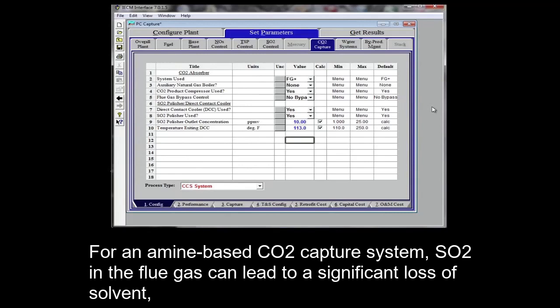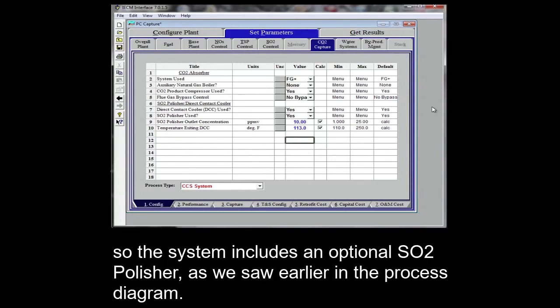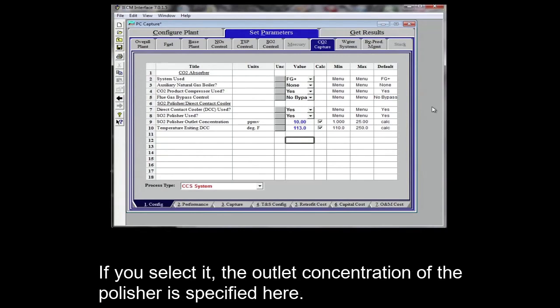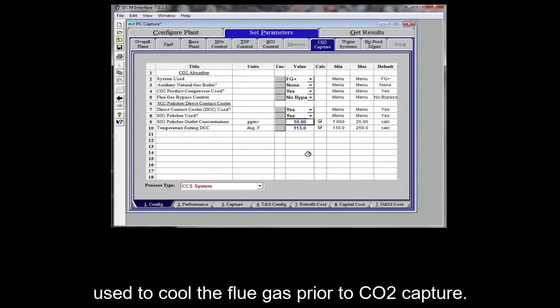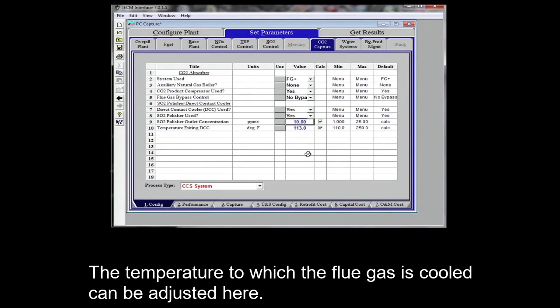For an amine-based CO2 capture system, SO2 in the flue gas can lead to a significant loss of solvent. So the system includes an optional SO2 polisher, as we saw earlier in the process diagram. If you select it, the outlet concentration of the polisher is specified here. In the system design, the SO2 polisher is coupled with a direct contact cooler used to cool the flue gas prior to CO2 capture. The temperature to which the flue gas is cooled can be adjusted here.